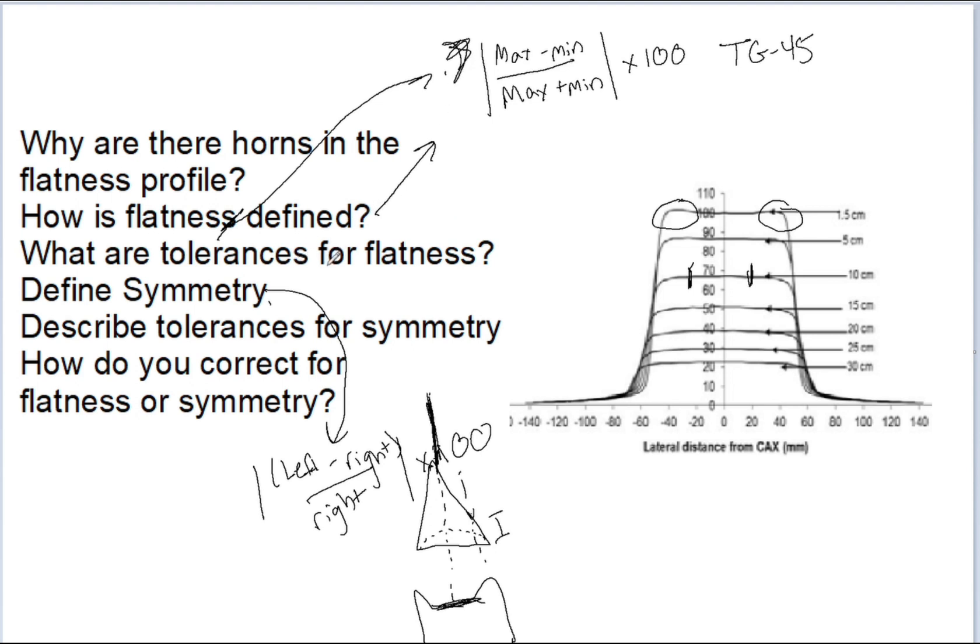Also, for the tolerances, it's good to know what the baselines are. You may look in TG-142, and it just says plus or minus 3%. Well, 3% of what? Does that mean 3% symmetry? No. It's 3% of your baseline value. That is important as well. Something they could definitely ask you further.